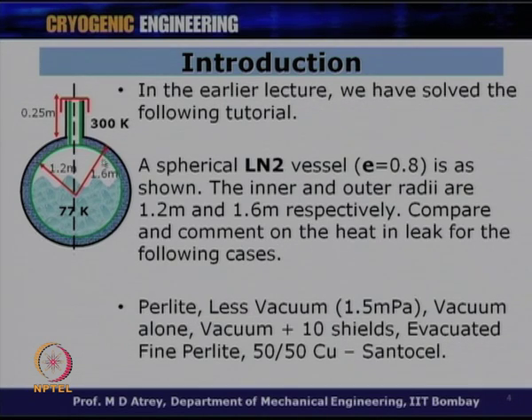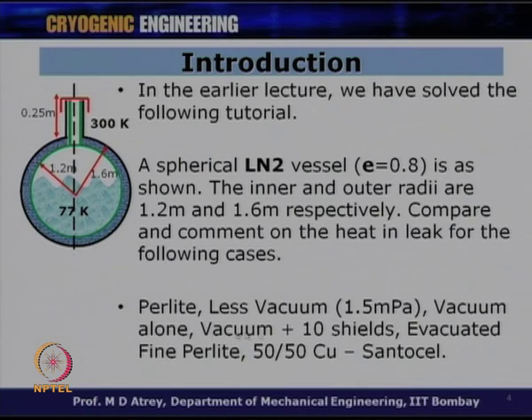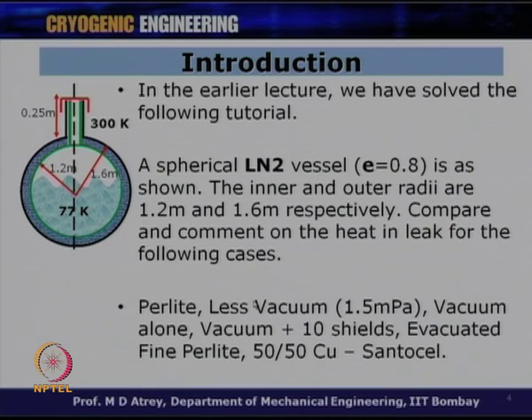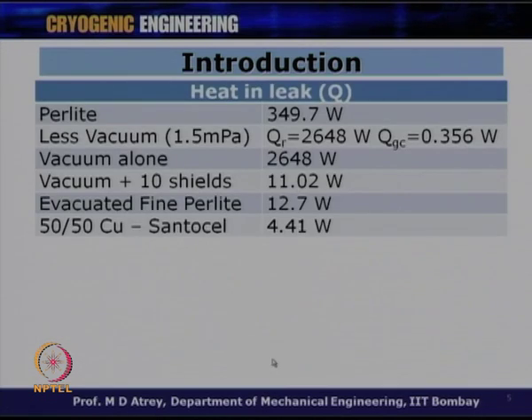The cases studied were: perlite as insulation with less vacuum at 1.5 mPa, good or perfect vacuum alone, vacuum plus 10 shields, evacuated fine perlite, and 50/50 copper santocel as opacified powder. We computed the heat in leak for all these insulations.